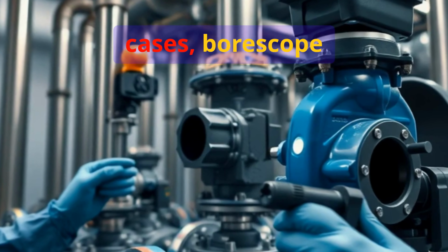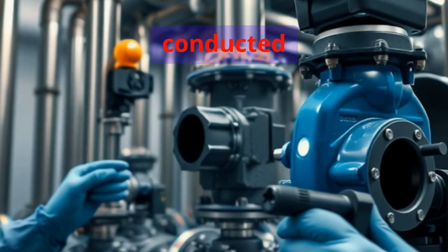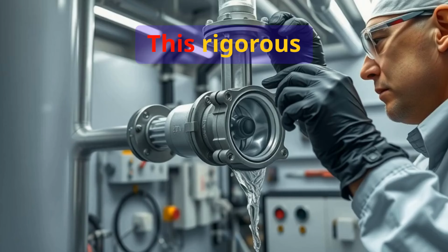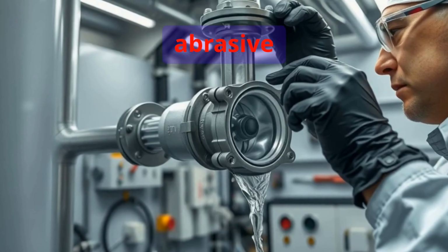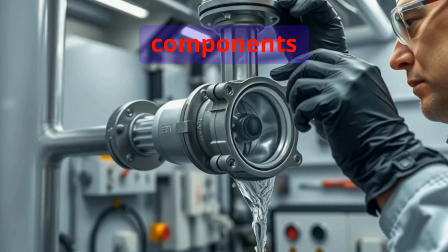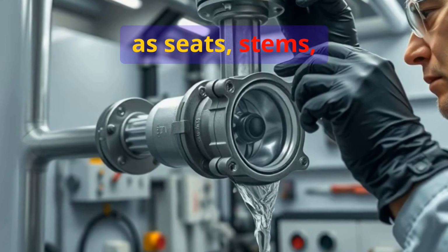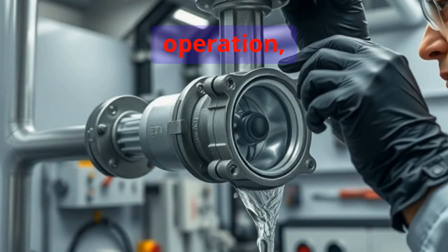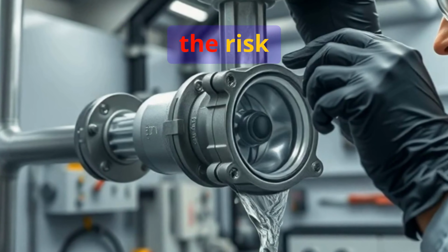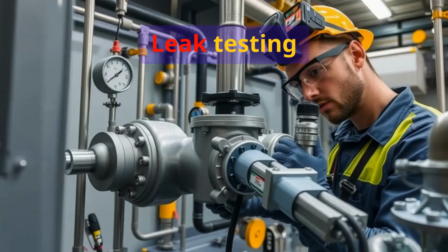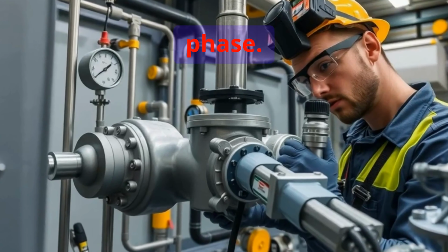In some cases, borescope evaluations are conducted for internal verification. This rigorous cleaning step prevents abrasive particles from entering sensitive components such as seats, stems, or actuators during initial operation, vastly reducing the risk of early valve failure. Leak testing is the next critical phase.